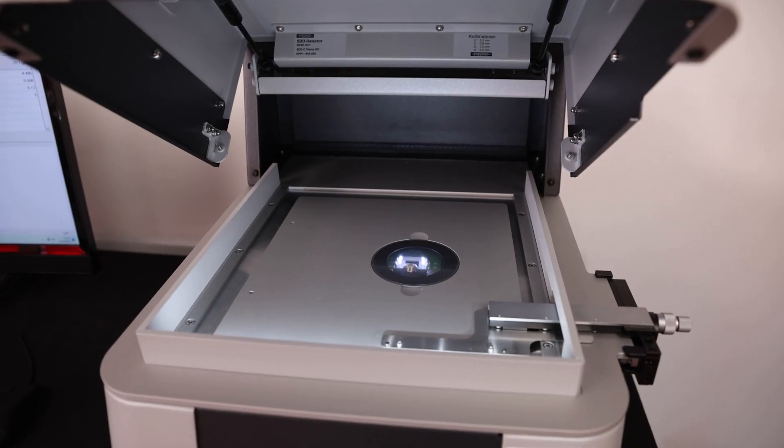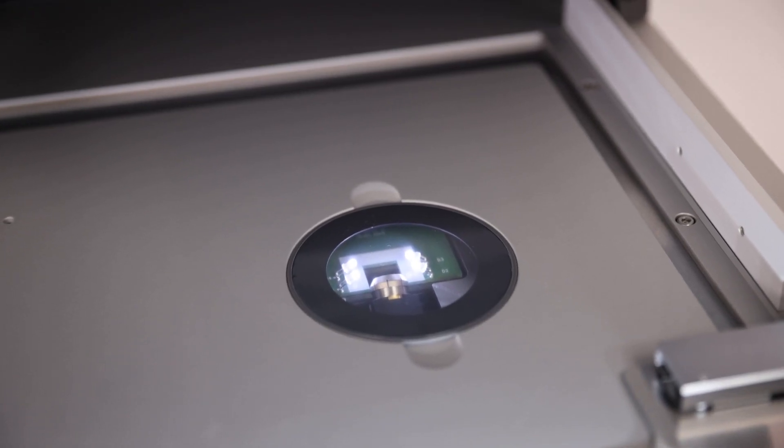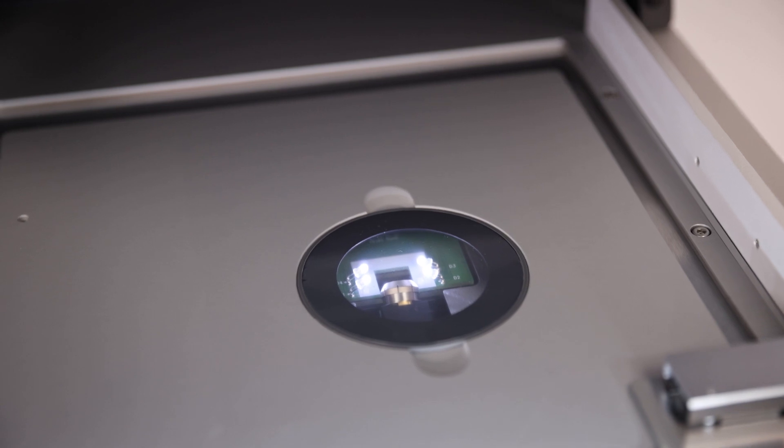The smallest sample areas can be analyzed thanks to a microfocus X-ray generator and a range of X-ray beam sizes provides optimum performance for a wide range of measurement tasks.